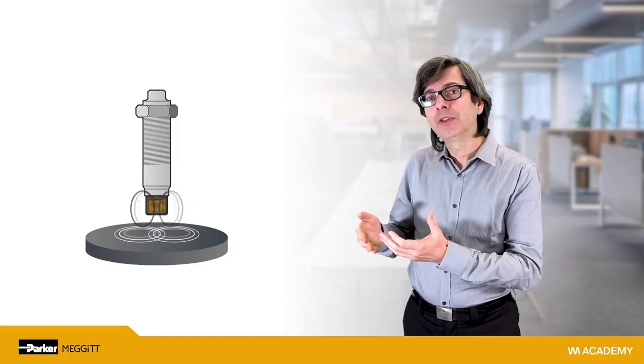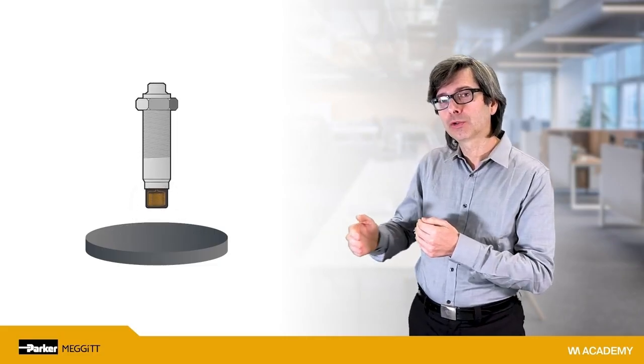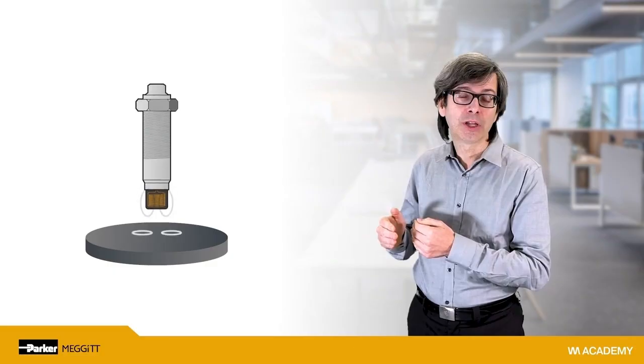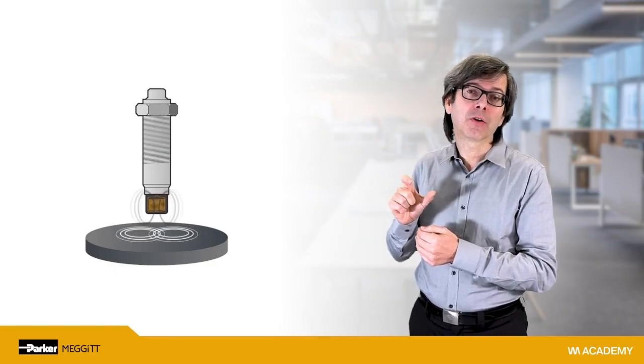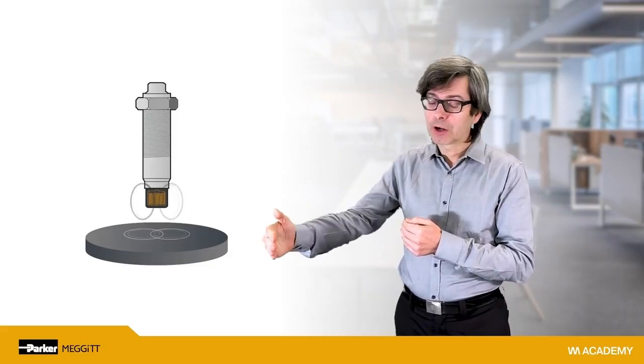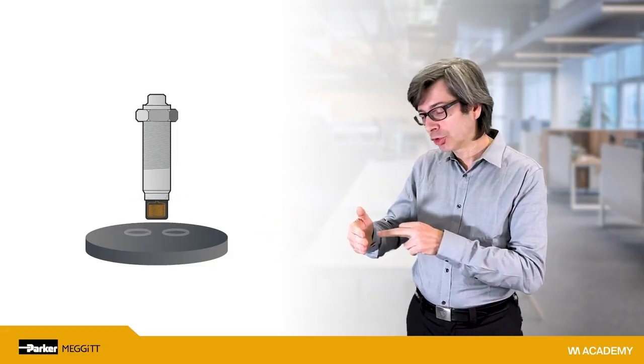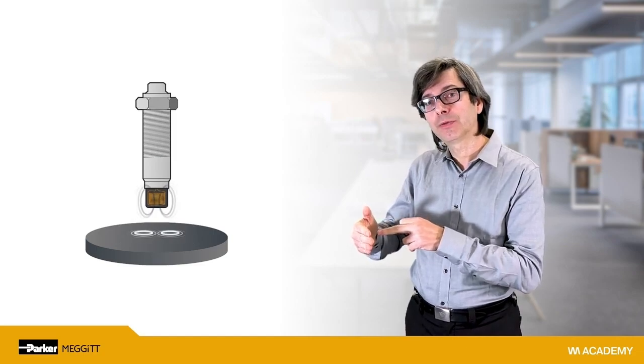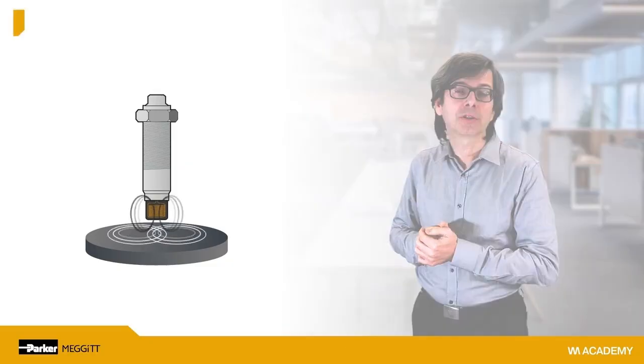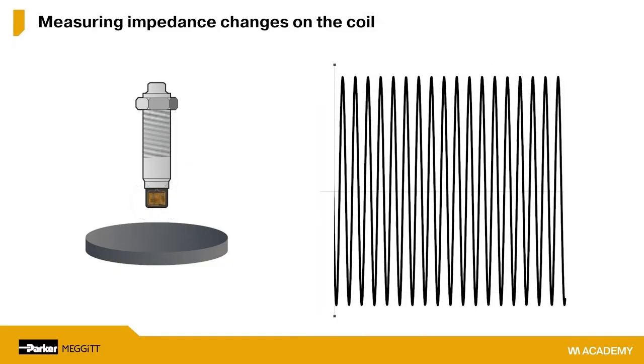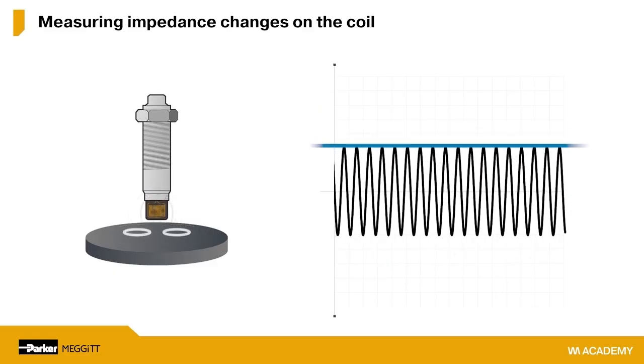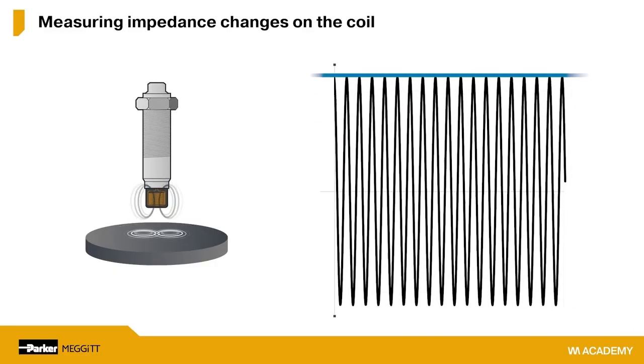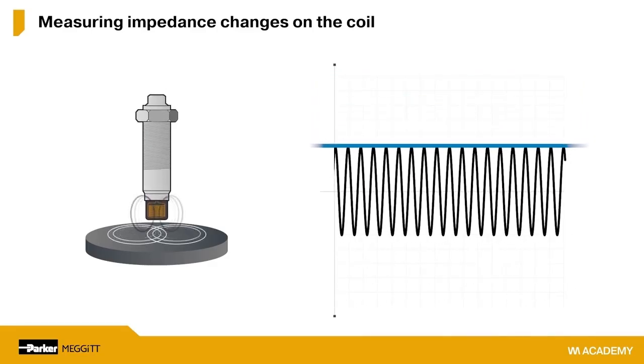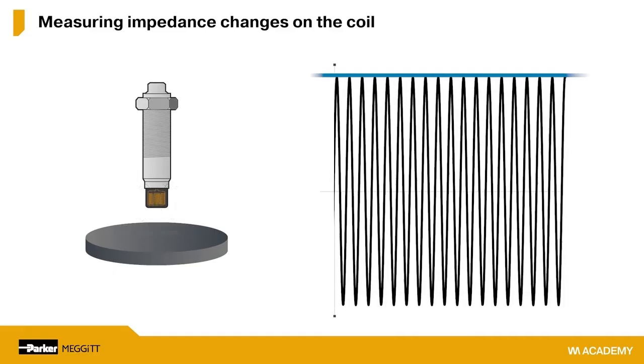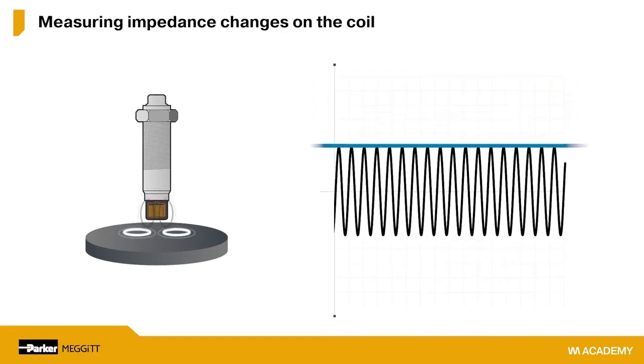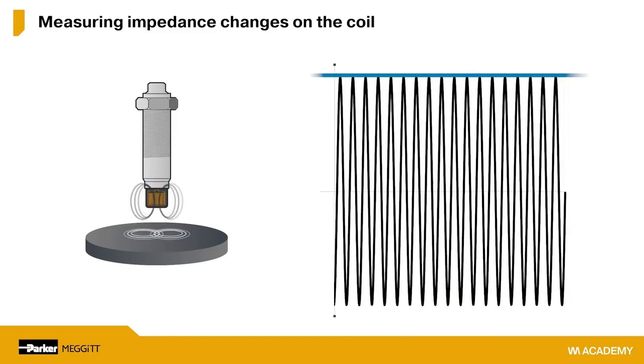The strength of that eddy current will depend on how close the target material is to the tip of the probe and will impact the impedance of the coil itself. So the closer the target material is, the stronger the eddy current on its surface, and the higher the impedance of the coil. To measure changes in the impedance of the coil, we can just measure the amplitude of the carrier signal. So if the target is closer to the tip of the probe, the amplitude of the carrier signal will go down. And this amplitude is represented in this animation as a blue line.